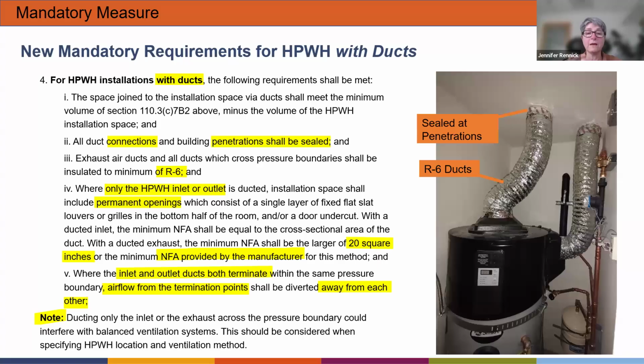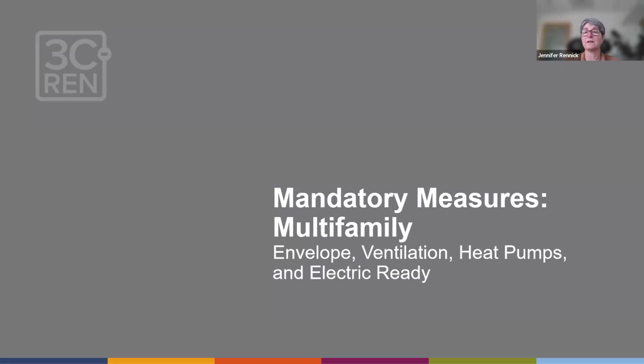So you can have a supply only, an exhaust only duct, or you can have a supply and a return or exhaust duct. And if you do that, then the code now is explicit in saying that the airflow from the termination points shall be diverted away from each other. So they're just putting what was common sense stuff in many ways into the code to now have something that people can look at. It also works as a checklist. So that section is applicable to all occupancy types, you know, multifamily, single family, and non-res.